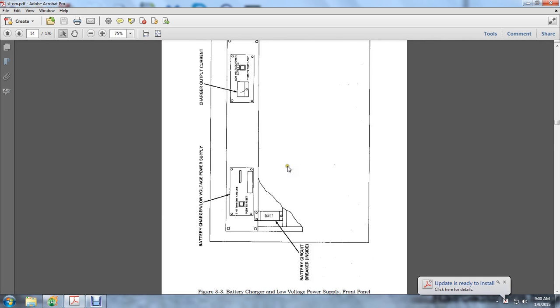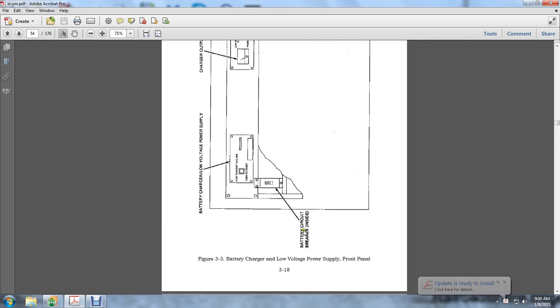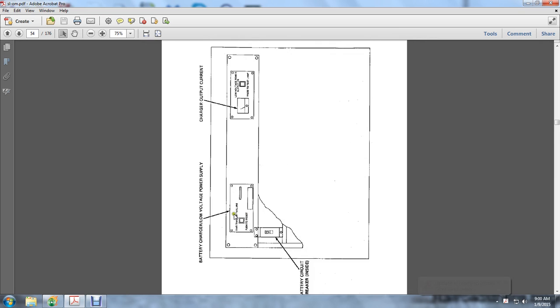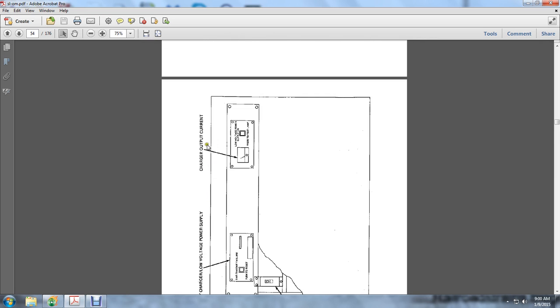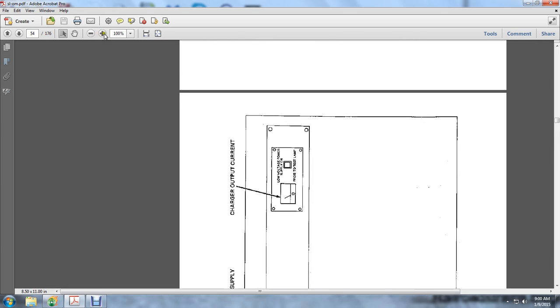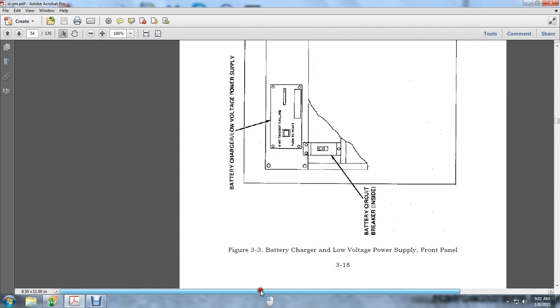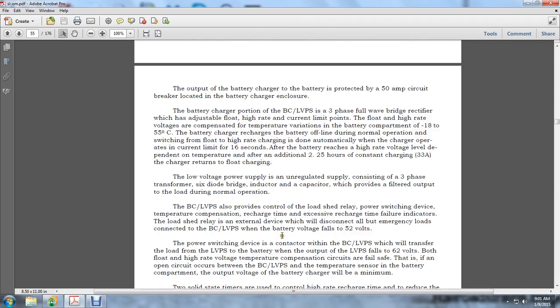Here you see a battery charger low voltage power supply front panel. The battery circuit breaker is inside the battery charger and low voltage power supply, along with the charger output current meter.